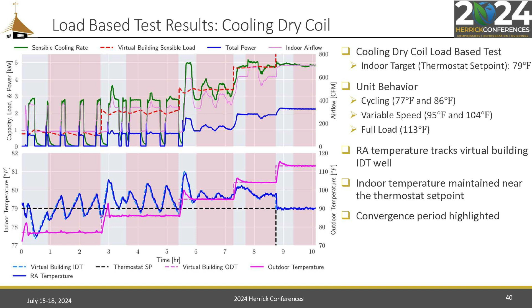They have a certain limit, and below that limit, if you have a smaller load that you're trying to meet, there's going to be some temperature change down, and the unit will respond. In this case, as the room temperature gets warmer, it will turn on. And so you can actually see that this is behaving like a real unit would in a real room. And as the load goes up, when you get to the third segment here, you can see that it's still hunting up and down, but it's not turning off. So it's now modulating and trying to meet the building load.